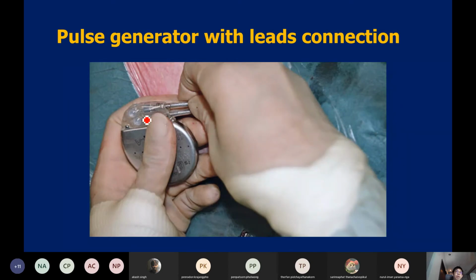Another important thing is that you have to put the lead into the channel as far as possible. You should not leave any space in the channel, because if there is some space, that means the connector might be loose or not locked in position properly, and this would cause loss of the connection. There might also be some air in the channel, and this air could cause noise in the generator. This is another important step. You have to put the lead all the way into the channel.